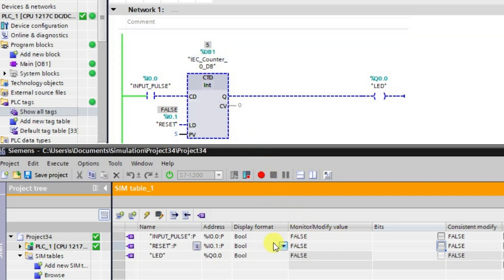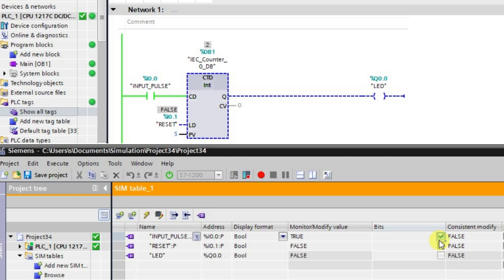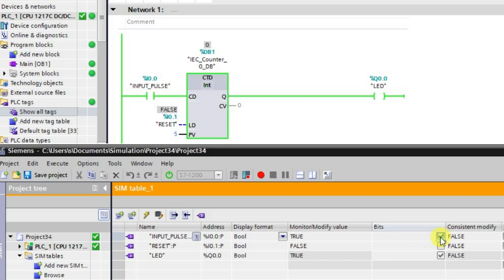Now we will give the input pulses. When you give the first input pulse it goes to 4, the next pulse takes it to 3, then 2 — in this way it moves in the negative direction. When the counter reaches 0, or the current value becomes 0 or less than 0, the output will be in the high state. You can see here — when it is 0 the output is high, and when it goes negative it remains high.